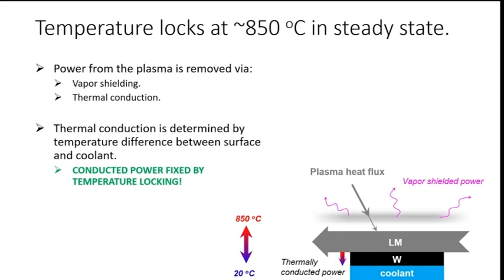Because you can easily destroy your sample if you put too much power into the coolant. You can imagine the water will heat up, especially where the plasma hits, and if it starts to boil — if you put too much heat — at some point you get boiling to such an extent that you have zero cooling anymore, and your component will just fail. So this is actually a great way to try to avoid that mode of failure.